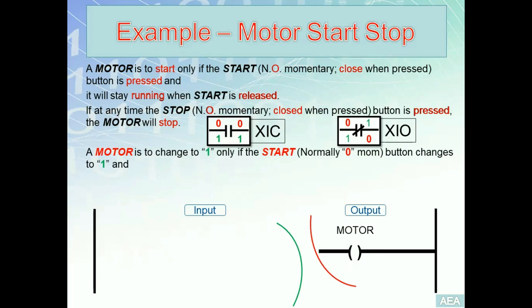The input section can be further divided into two virtual sections: an on section and an off section. In our planning, we group all inputs responsible for energizing the motor together, and all inputs responsible for de-energizing the motor together. Per this requirement, the motor is to change to one when start changes to one. The input involved is start, which belongs in the on section. The question is: XIC or XIO?